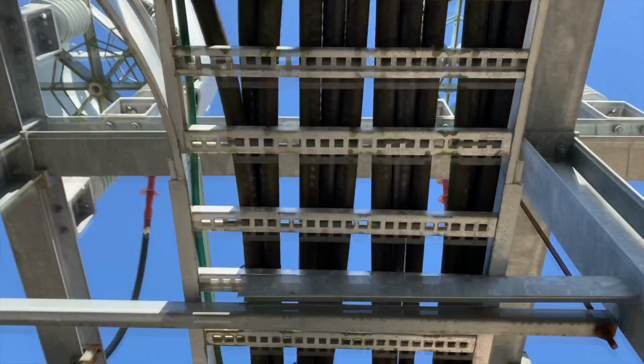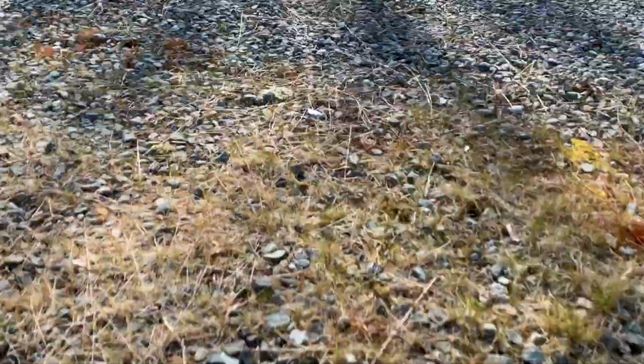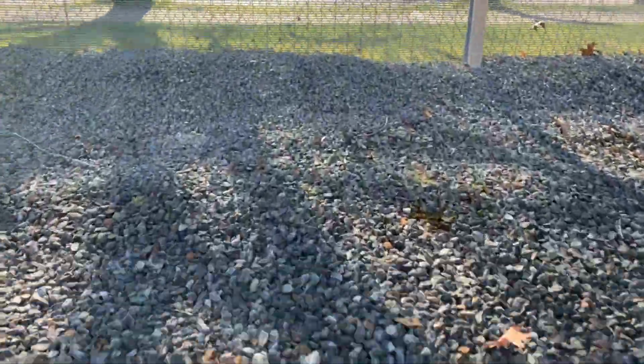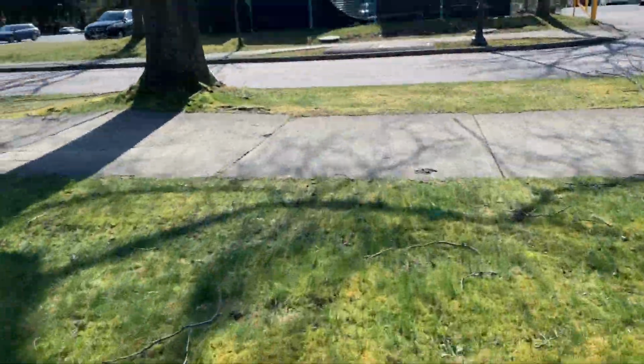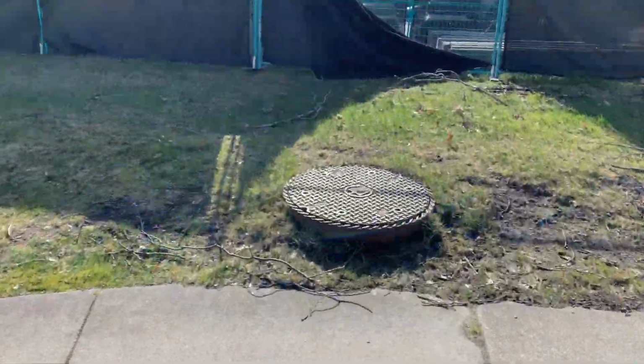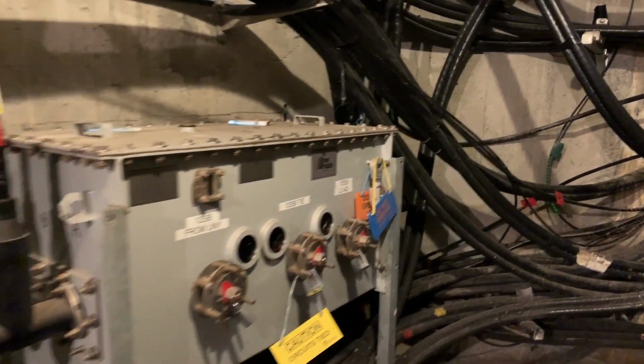Each breaker connects to large feeder cables that run from UNY throughout the campus via underground banks of conduits called duct banks. There are 14 main feeders and 3 standby or backup feeders distributed across campus. The duct banks connect to a network of 300 manholes across campus, the largest of which is right out front of UNY. This manhole hosts every feeder circuit before they dispatch to different areas of the campus.